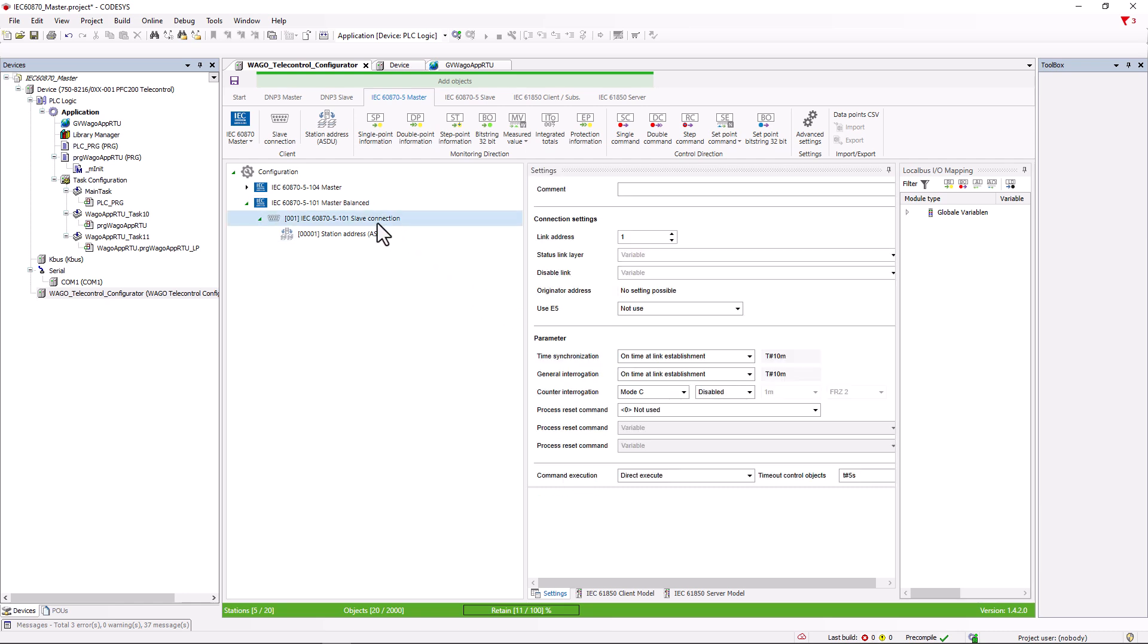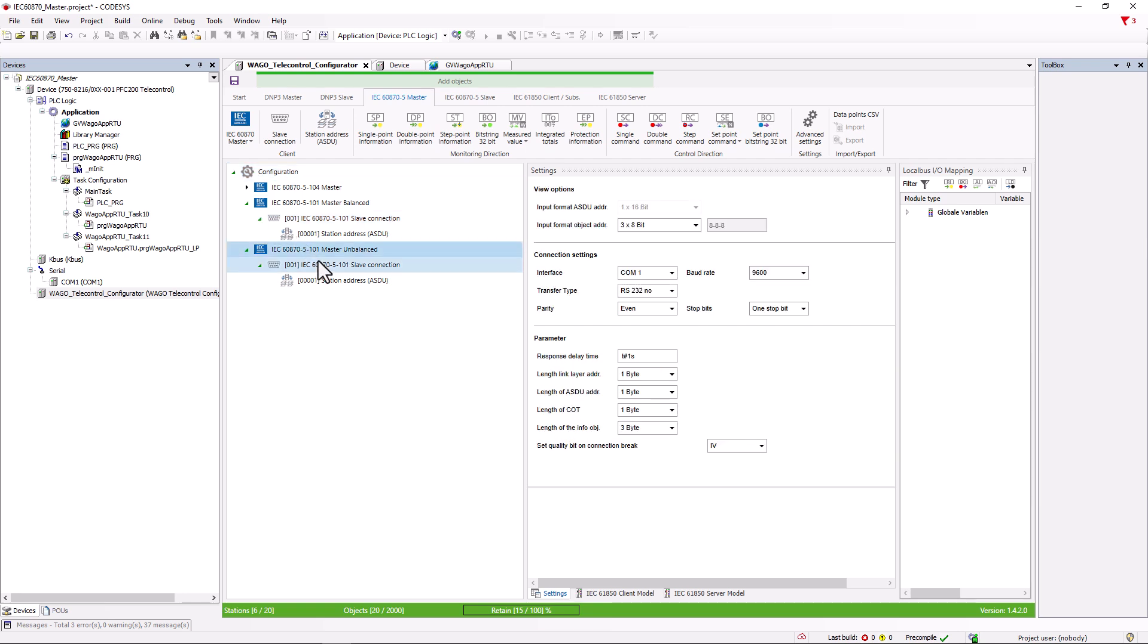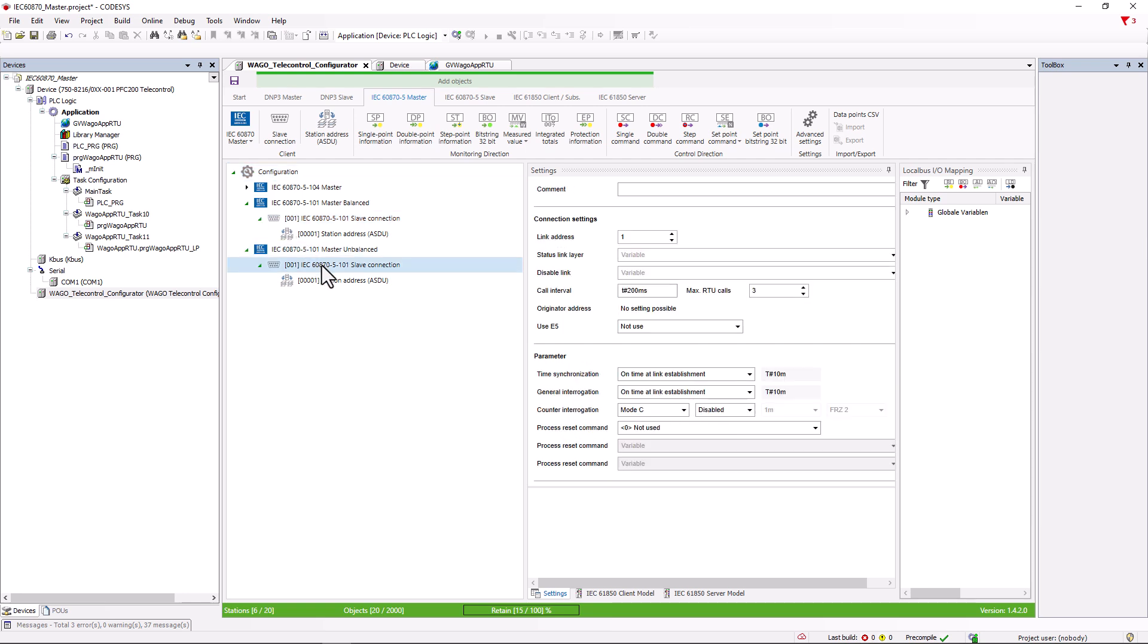The settings for the Slave connection are then almost identical to those for the 104 protocol. If we now look at unbalanced communication, the call interval is added at this point. In unbalanced communication, the slave is polled cyclically to see if it has anything to report. This method, known as polling, allows more than two participants to be connected, unlike symmetric communication. How often this happens per second is determined by the polling interval, that is the call interval. The default is 200 milliseconds.